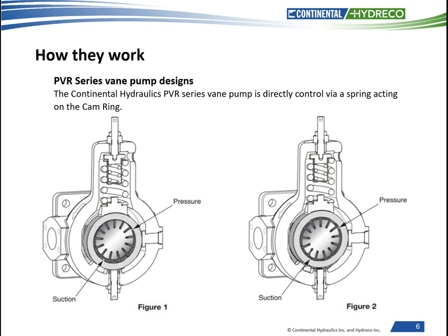The reason this is a critical key feature is: as the vanes transition from the suction port area over to the pressure port area, the critically designed port plate at one specific point ports pressurized oil to the bottom of each vane, generating a higher force to push the vanes outward against the cam ring. Because of the walking ring technology, this one point where the vanes are forced out against the cam ring is then evenly distributed around the entire ID of the cam ring, resulting in minimal wear.